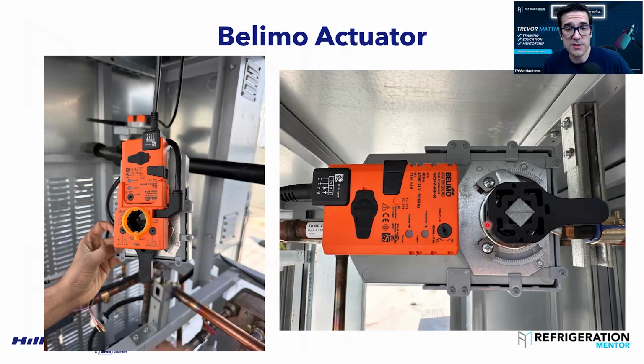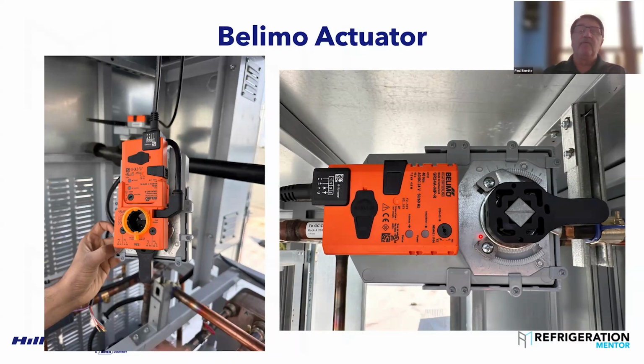Yeah. And these are different strategies, and you can manually open these, right? Because if you're doing a startup, you want to test it. Can you manually open it just to see if it moves? Well, yeah, you can, but some of these three-way valves are quite stiff until they get worked in with the heat and some motion. But on the top of that valve on the right side, that back switch, you can push that in and manually manipulate the valve. You can also push it in and lock it in place, which will override and not let you do anything with that valve.